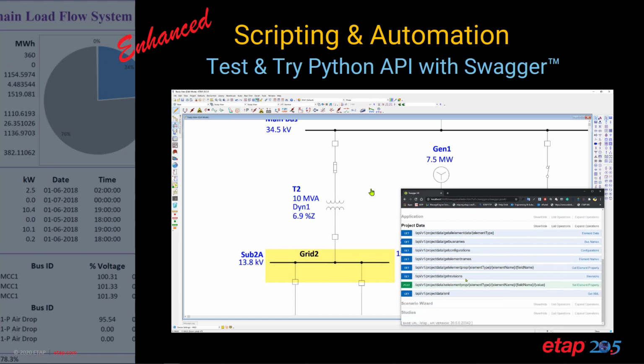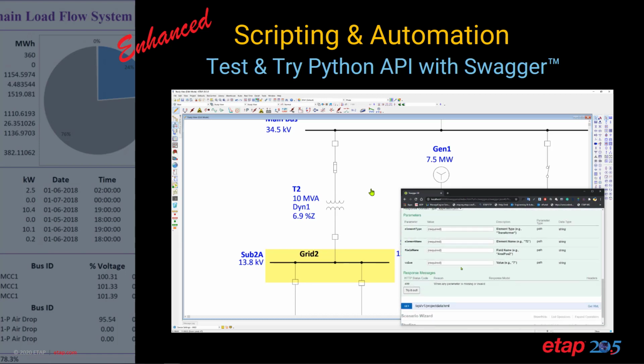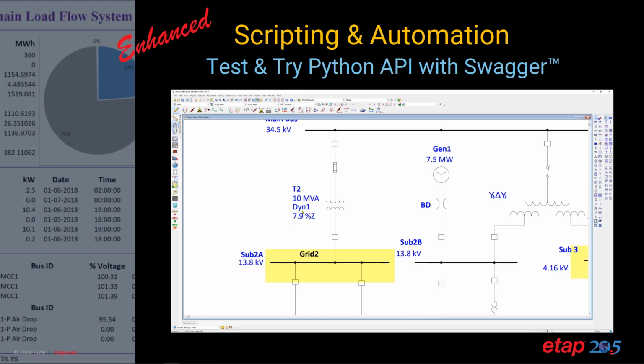You can also try another one to set element properties. We'll type in transformer and select transformer T2. The field we'd like to change is the positive impedance, setting it to a value of 7.9. As soon as you execute, you'll see on the diagram the value switch from 6.9 to 7.9. With this, you can quickly try commands if you're not familiar with Python, or start writing Python code yourself.